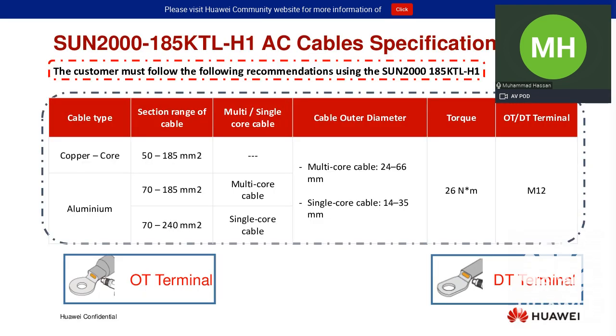Coming to the AC cables, we recommend two types of AC cables: copper cables and aluminum ones. You can use the copper cable. The selection range for the copper cable is from 50 to 185 square millimeters, and for the aluminum one, for the multi-core it will be 70 to 185 square millimeters, and for the single core it will be 70 to 240 square millimeters. The cable outer diameter for the multi-core is recommended from 24 to 66 millimeters, and for the single core it is 14 to 35 millimeters.